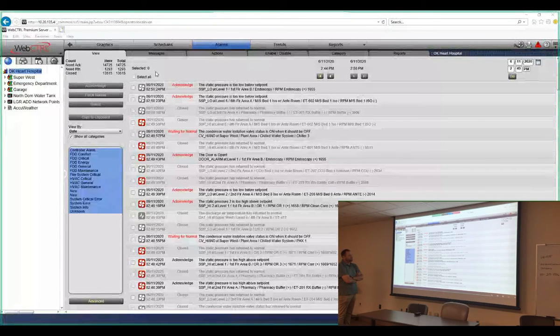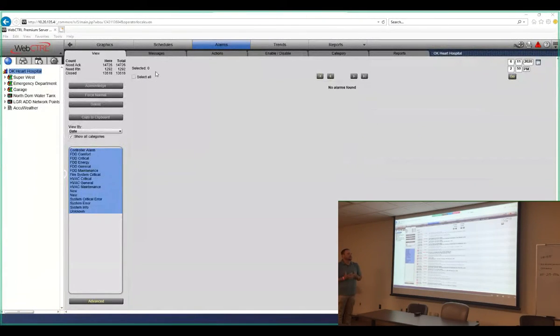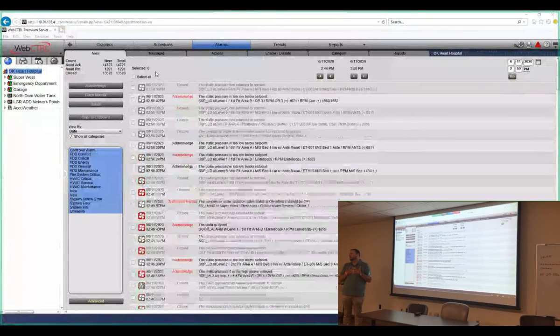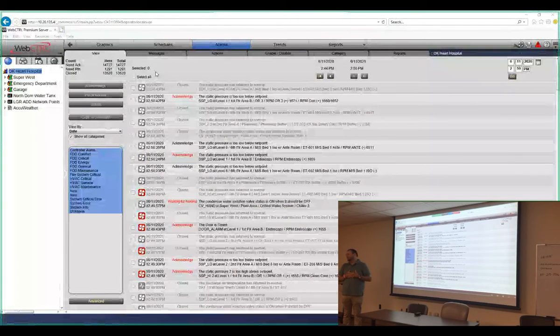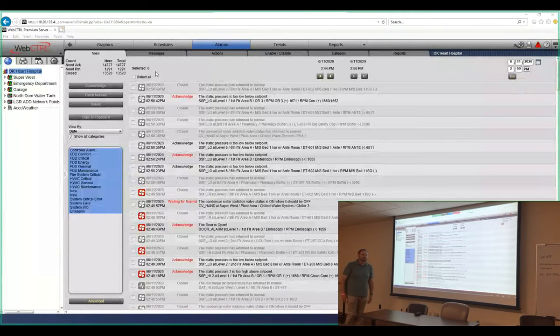Yep, so that's what a lot of these are, we've got to hone this list down. A lot of it is global modifying, so for every space temperature, if I don't want to alarm it for 5 or 10 minutes, I can change every one of them in the whole building in one shot. Same with all the door alarms, I can change them all in one shot. It's just a matter of figuring out what those timeframes need to be so we get rid of those nuisance alarms.